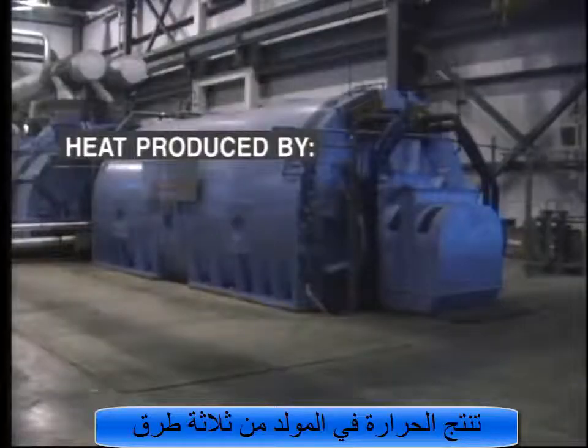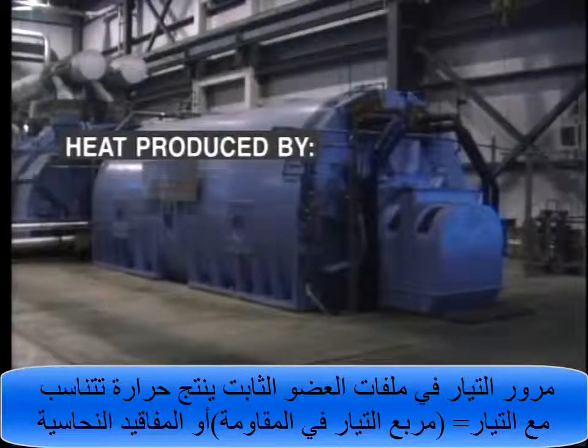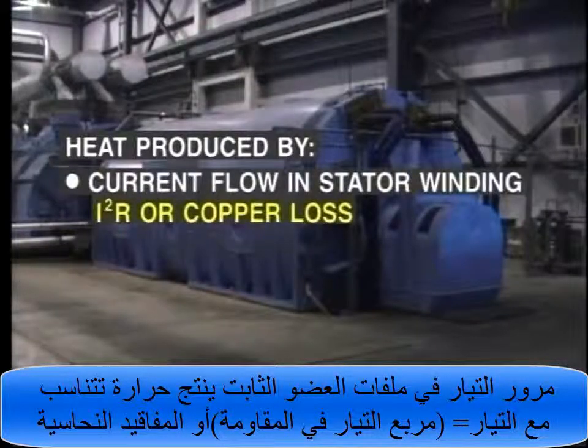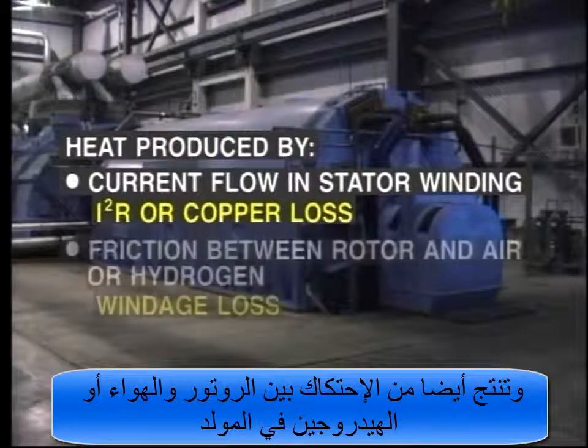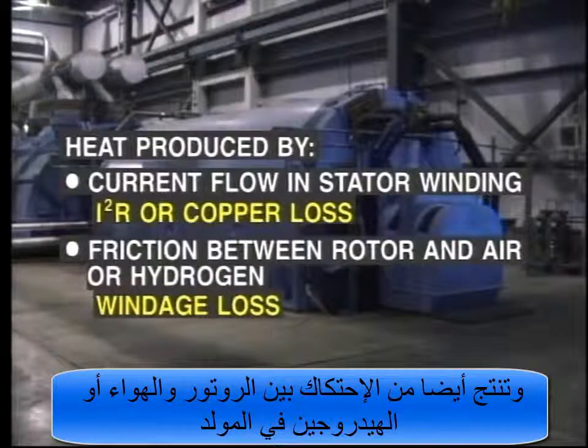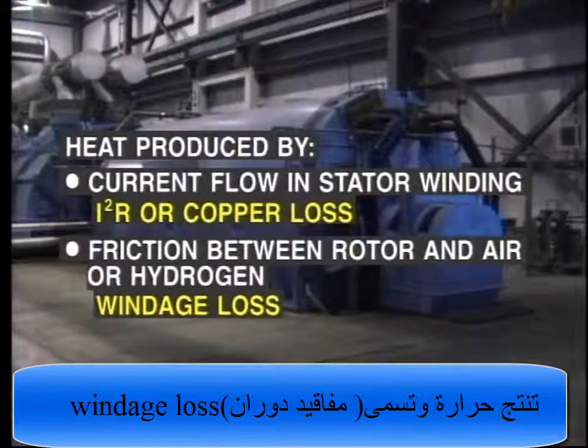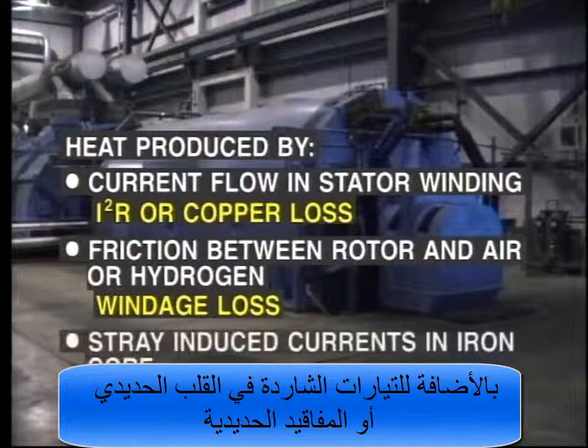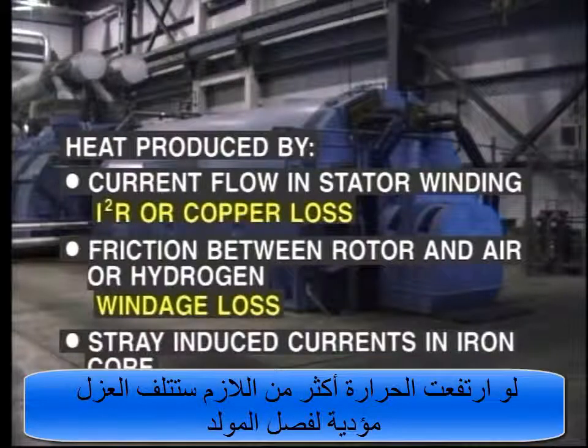It is produced within the generator in three ways. Current flowing in the stator winding produces heat, which is proportional to the square of the current. This is the I squared R, or copper loss. Friction between the spinning rotor and the air, or hydrogen, in the generator produces heat called windage loss. Stray induced currents in the iron core produce heat called iron loss.